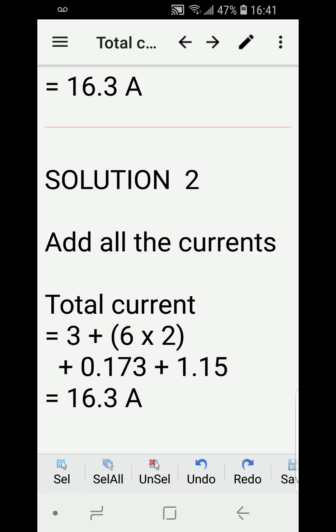Solution 2 is to simply add all the currents together. Total current equals 3 amperes (mullion heater) plus 6 times 2 (the two defrost heaters) plus 0.173 amperes (evaporator fan motors) plus 1.15 amperes (fluorescent lights). Adding them all together, we arrive at the same answer of 16.3 amperes. I hope you learned something from this — till next time, thank you!